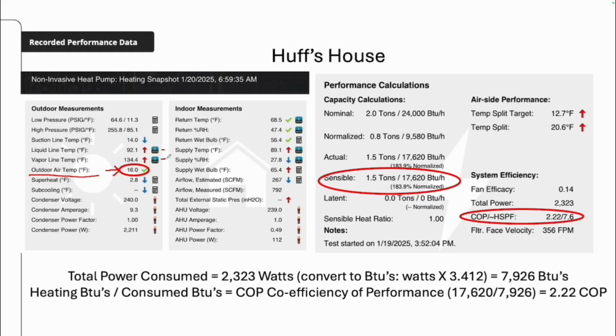And so I keyed that in. And then when I did non-invasive, I was actually taking line temperatures as well, so I could kind of see what was going on. But here are my air probes. And you can see that I was using Fieldpiece air probes. You can tell by the little icons here. And so again, when you're doing non-invasive, not only do I want to take temperatures, I do also like taking electrical data, because it's not only going to give us delivered capacity, but it'll actually calculate the efficiency, system efficiency as well. And so look at how impressive this information is on this non-invasive report.